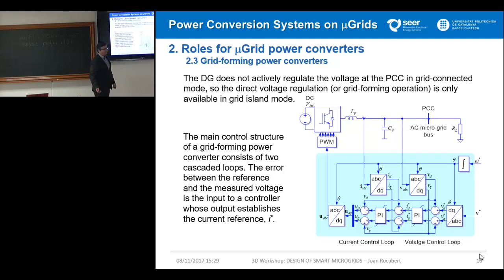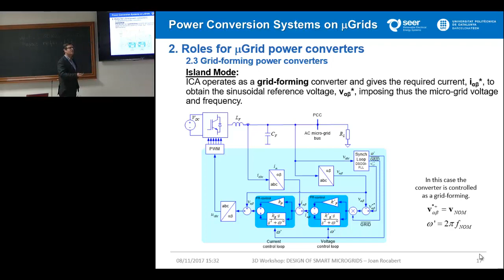This is the same structure as the island mode, but the grid forming mode, in this case in alpha beta, so we get the resonant controllers. The voltage and frequency in that concept are being imposed by some variable from storage, but as I said, this variable can come from a higher control level.